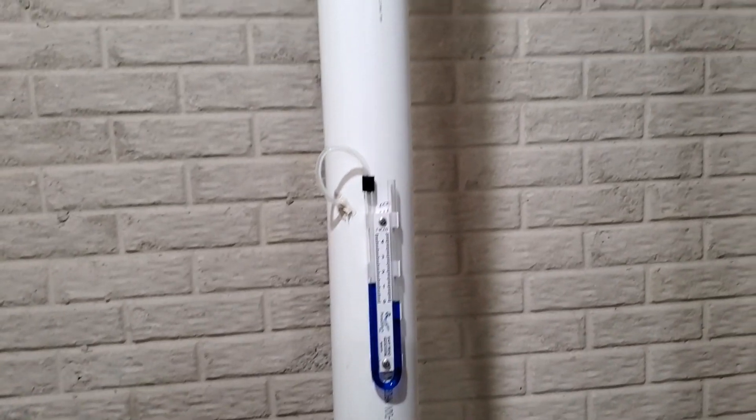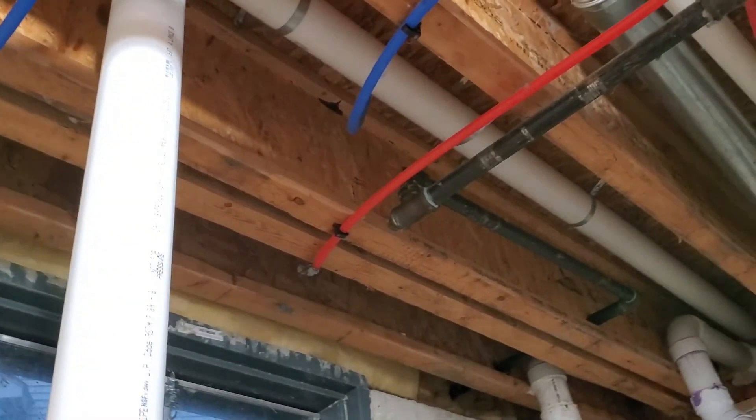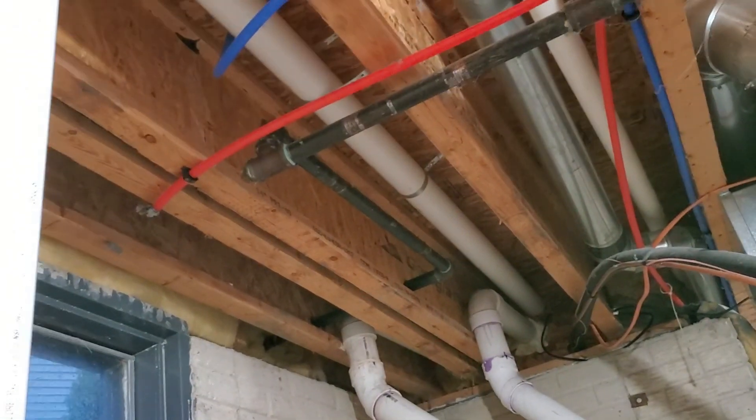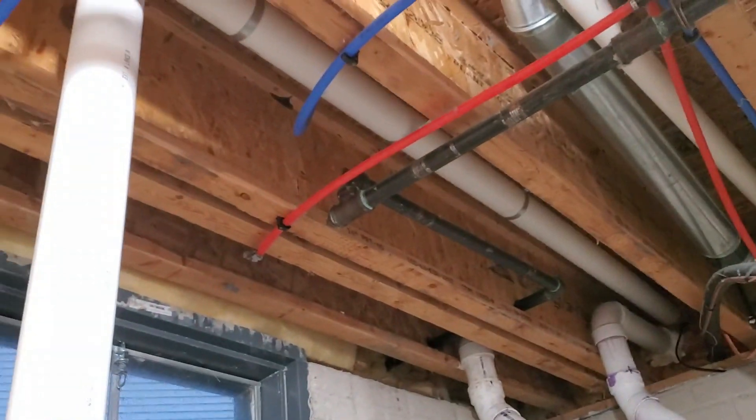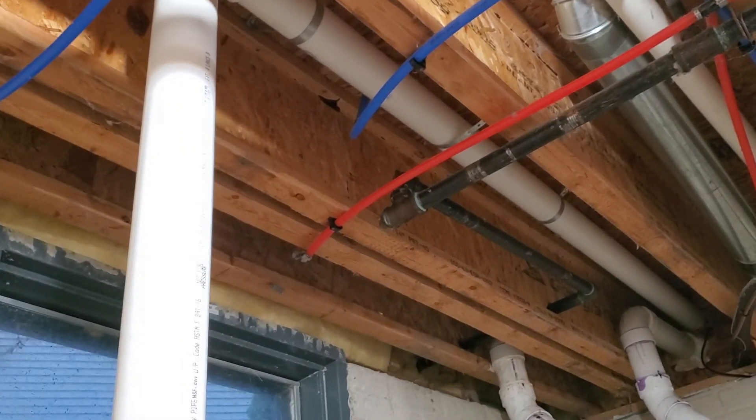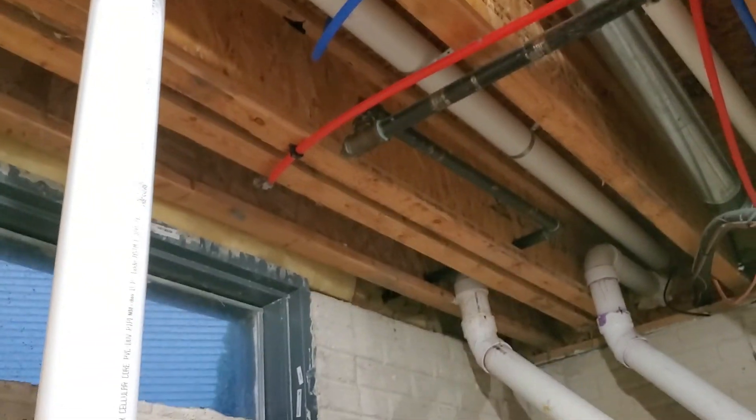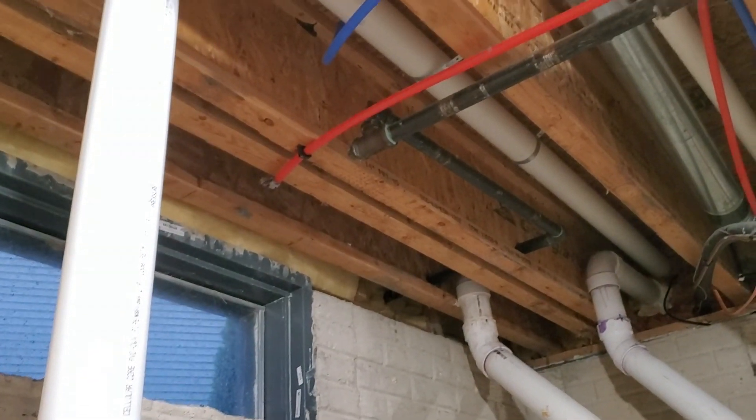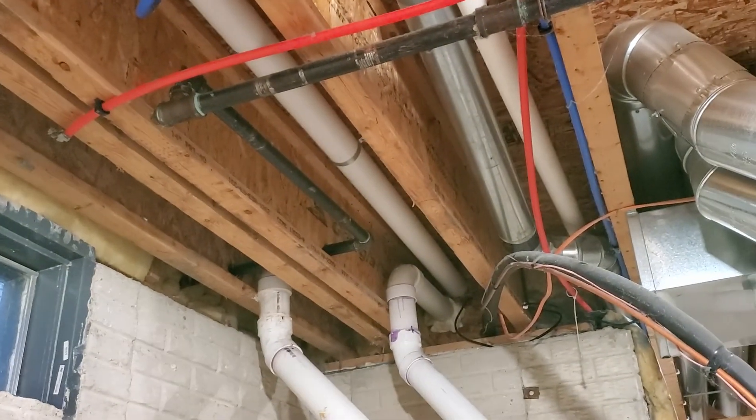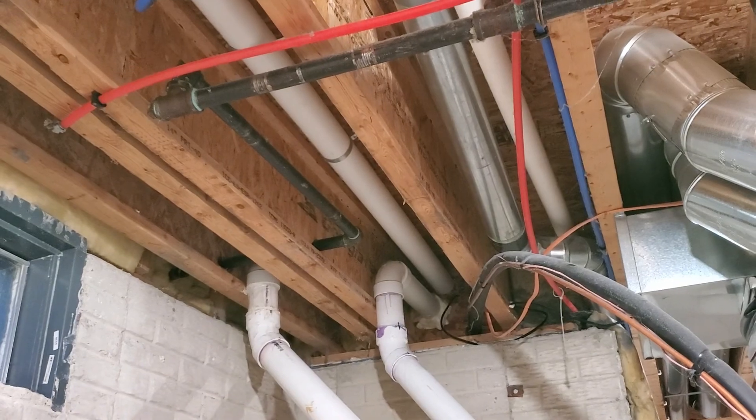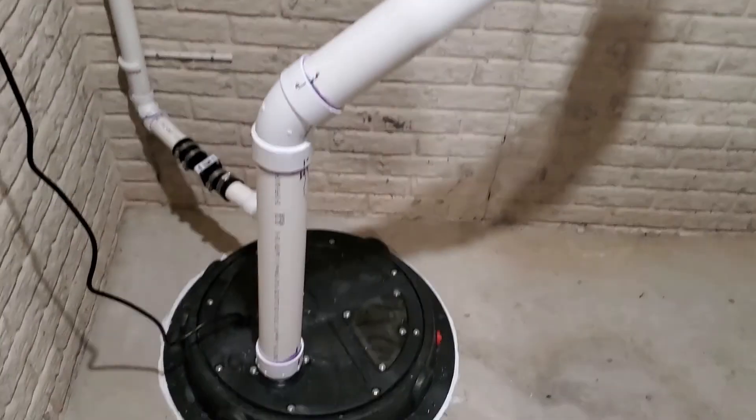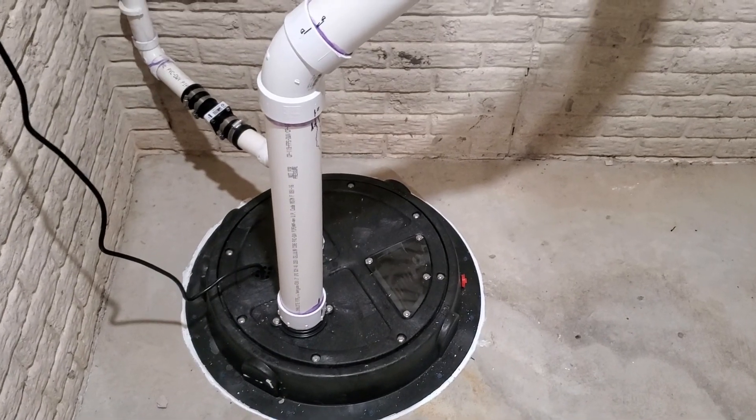We run up and between the joists here. I've got this sloped a little bit, probably an eighth inch per foot back towards the sump pit, so any condensation that forms outside or in the fan runs all the way back down and will just drain into the sump pit.